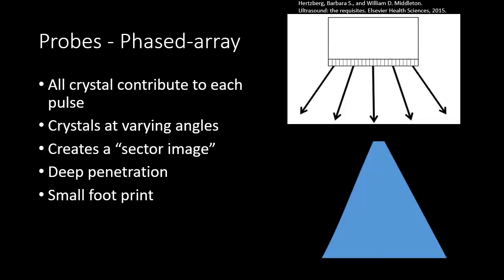The phased array probe has multiple crystals along the surface of the transducer that all fire together to generate a pulse. The crystals can send pulses out at varying angles to create a sector image. Phased array probes are traditionally lower frequency probes that allow for better penetration deeper into the soft tissues, but tend to have lower resolution than a linear probe. A key advantage is their small footprint, allowing imaging through narrow sonographic windows such as fontanelles in pediatrics or rib spaces in chest imaging — providing a wide field of view with high penetration at a sacrifice of resolution.